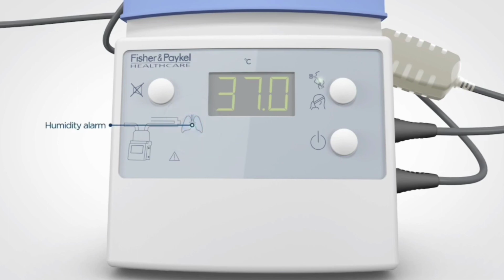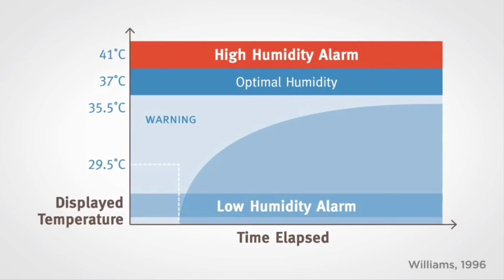Humidity alarm. A humidity alarm indicator will light up when the humidifier cannot deliver optimal humidity. This occurs when the delivered temperature is above 41 degrees centigrade or below 35.5 degrees centigrade. An audible alarm may be heard depending on the duration and severity of the humidity condition, as defined by the work in the Williams paper. That is, a temperature and associated humidity level above 35.5 degrees centigrade is acceptable indefinitely, while a temperature below 29.5 degrees centigrade is unacceptable, even for a short time.